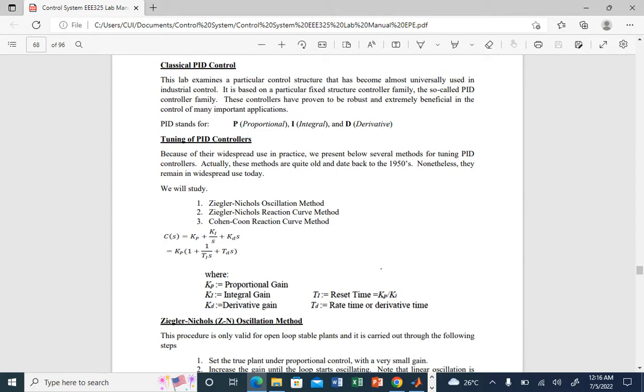There are two formulations. The first is KP, KI/s, and KD·s. The second, which we normally use, takes KP outside and has the form KP times (1 + 1/(TR·s) + TD·s). Here KP is the proportional gain, KI the integral gain, KD the derivative gain. TR is the reset time, equal to KP divided by KI, and TD is the rate or derivative time.